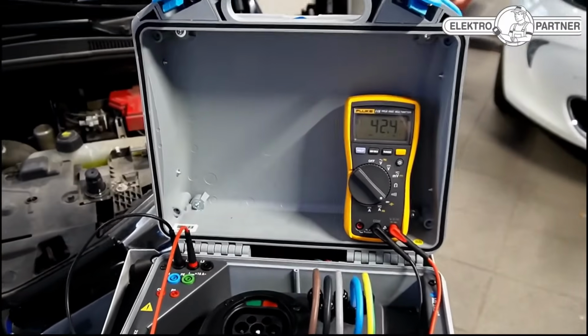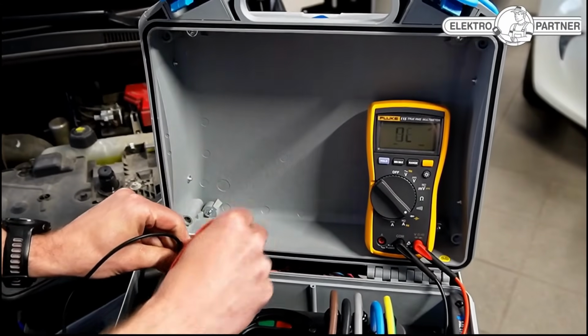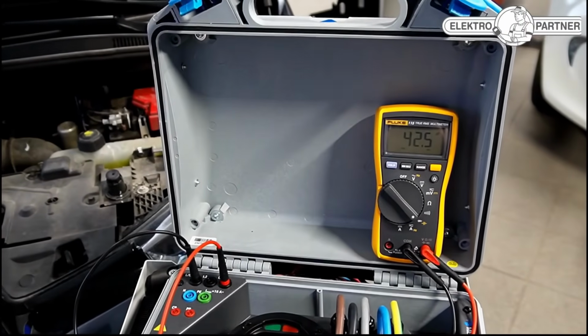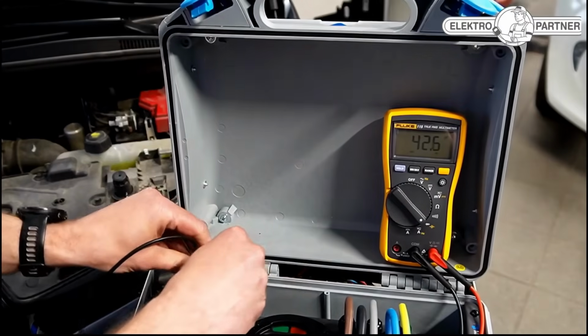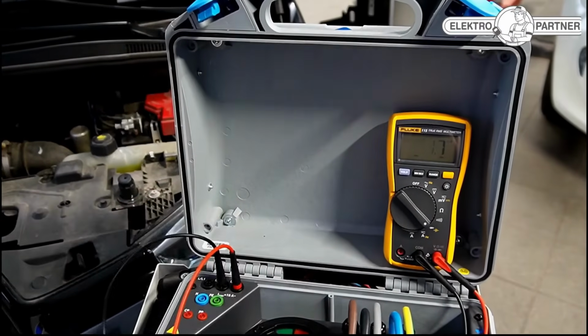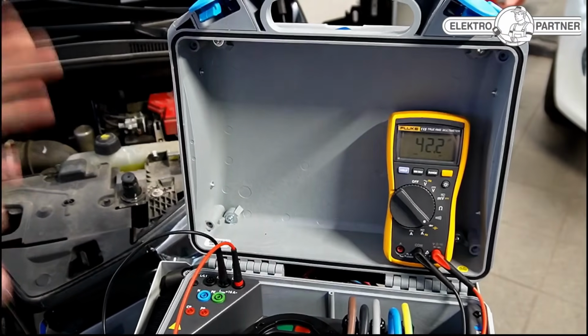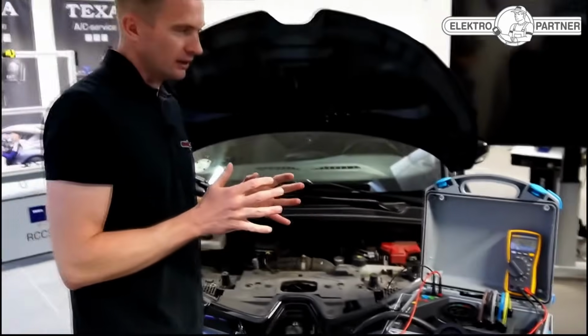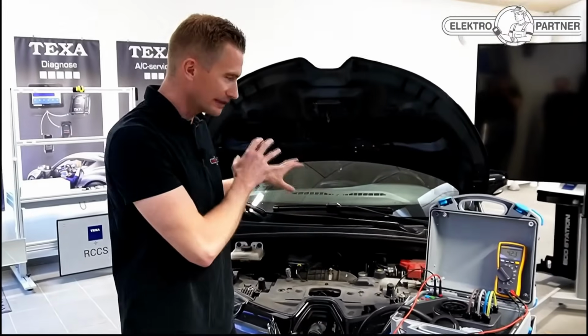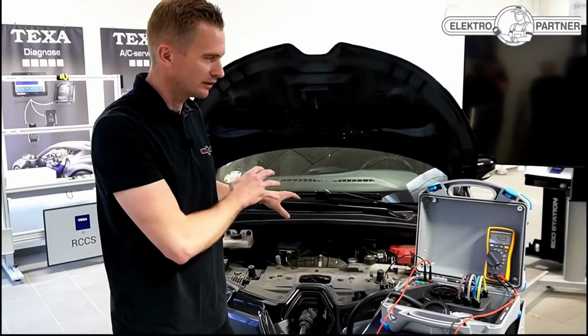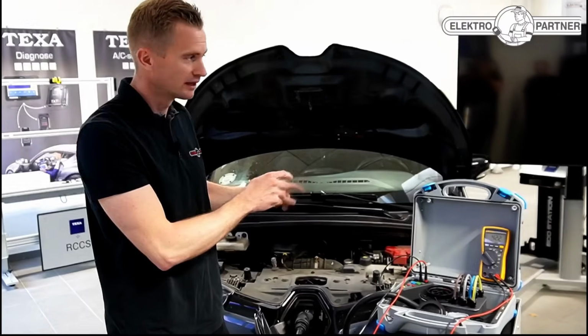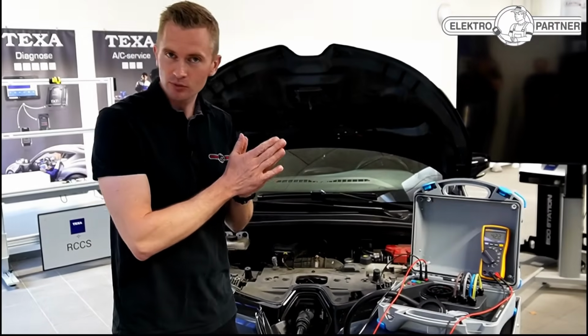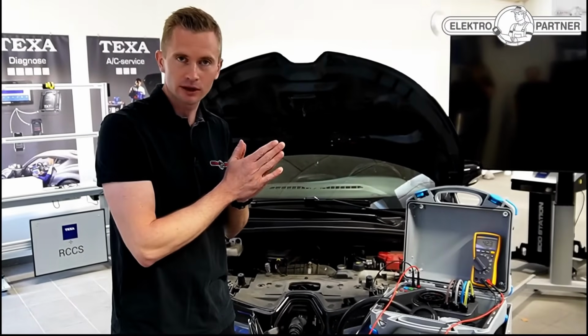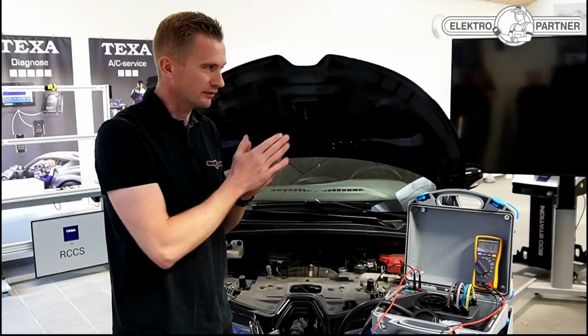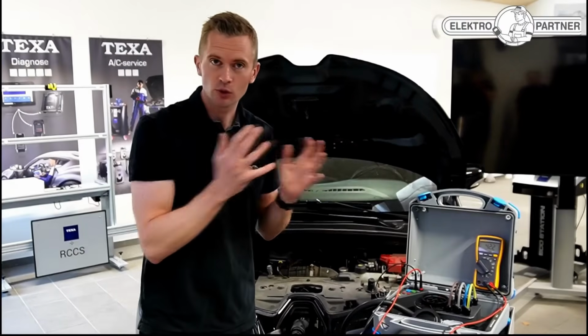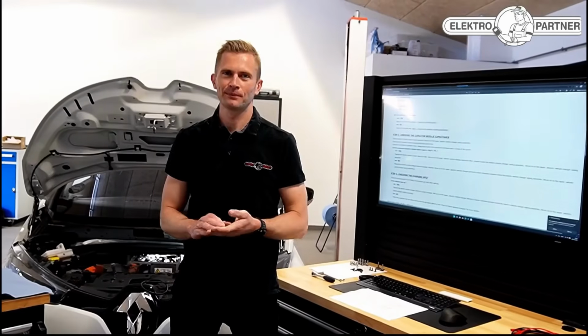Phase 1 to 2, we measure 42 microfarads. Phase 1 to 3, 42 microfarads. And phase 2 to 3, 42. That's actually pretty precise. So based on this, I have to say that this one measures exactly 42 microfarads between all the phases, whereas with the other one, we actually had a small difference between one of the phases, at about 7 microfarads. So there was a slightly bigger difference on the car with the fault, we can conclude.